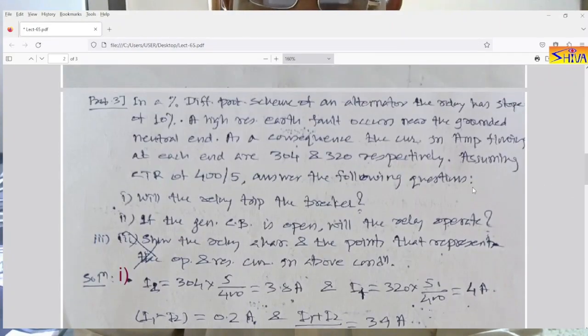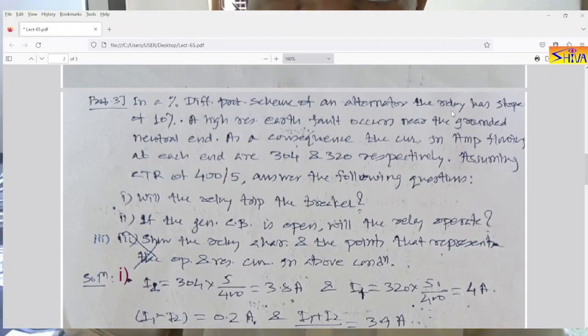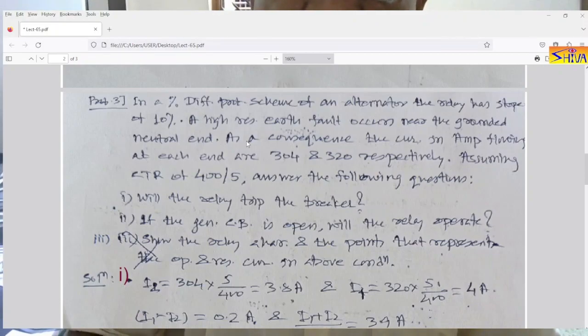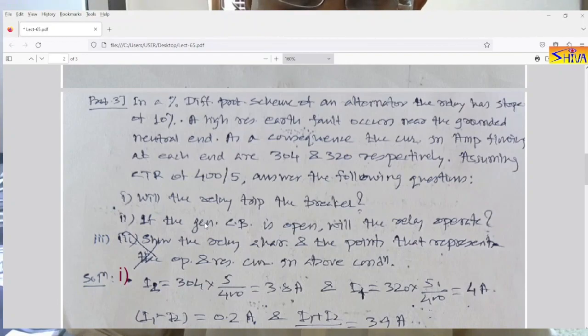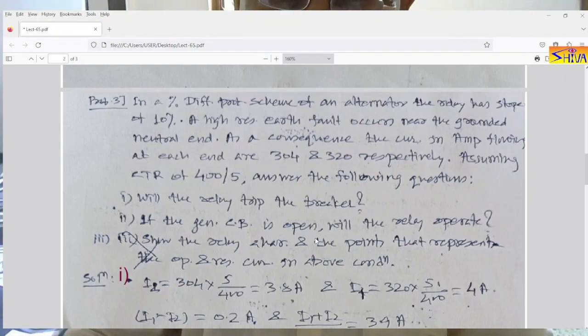Third numerical — and this is a very good one. In a percentage differential protection scheme of an alternator, the relay has a slope of 10%. A high-resistance earth fault occurs near the grounded neutral end. As a consequence, the current flowing at each end is 304 amperes and 320 amperes respectively. Assuming a CT ratio of 400/5, answer: (1) Will the relay trip the breaker? (2) If the generator circuit breaker is open, will the relay operate? (3) Show the relay characteristic and the points representing operating and restraining current in the above conditions.